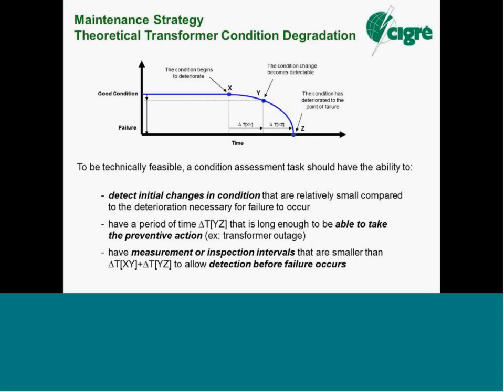Is it easily maintainable itself? You've got a maintenance cost for the monitoring system itself, let alone the transformer maintenance. Then there's the life of these devices, as they are electronic devices. If you consider the life of chips and electronic equipment in an environment of electromagnetic fields, in an outdoor situation, relying on the IP rating of the housing and so on to protect from the elements.